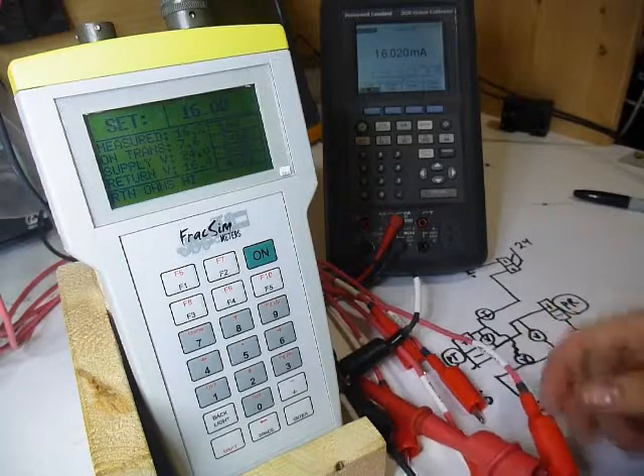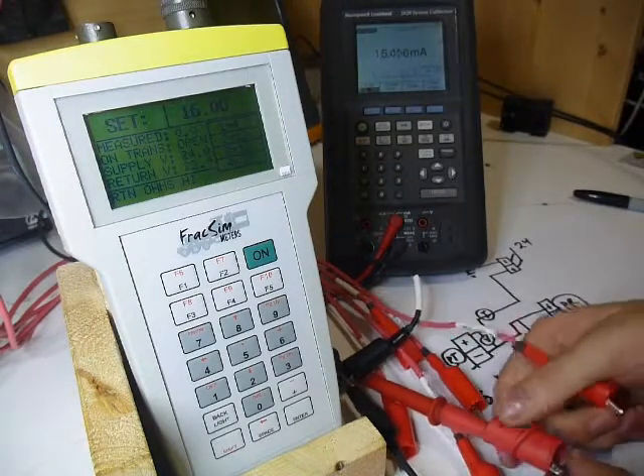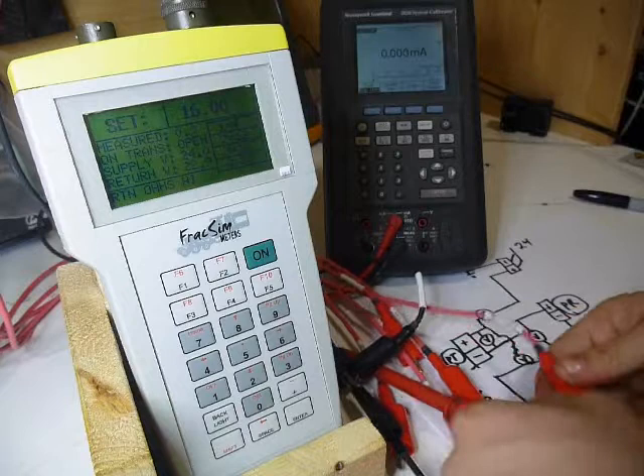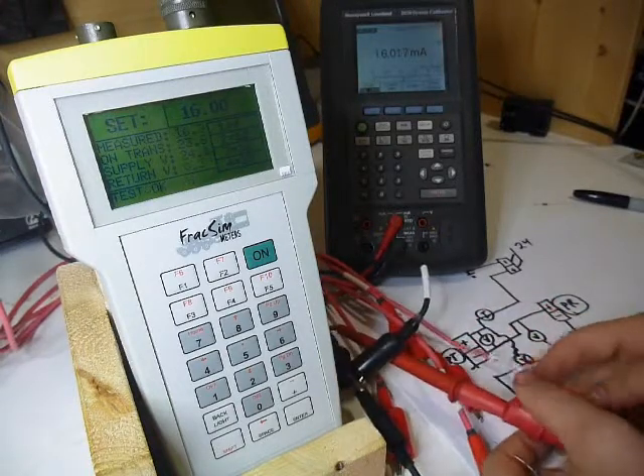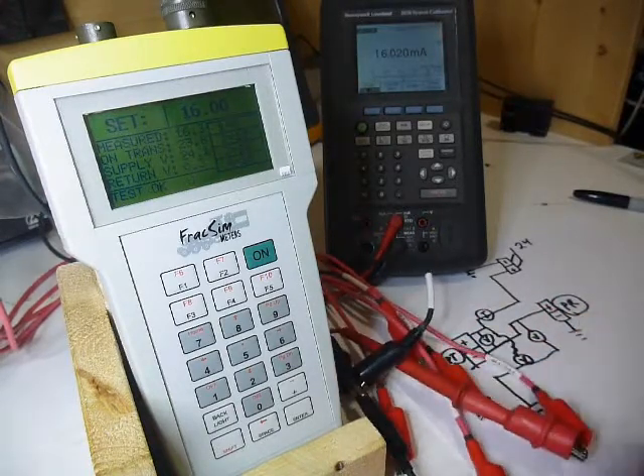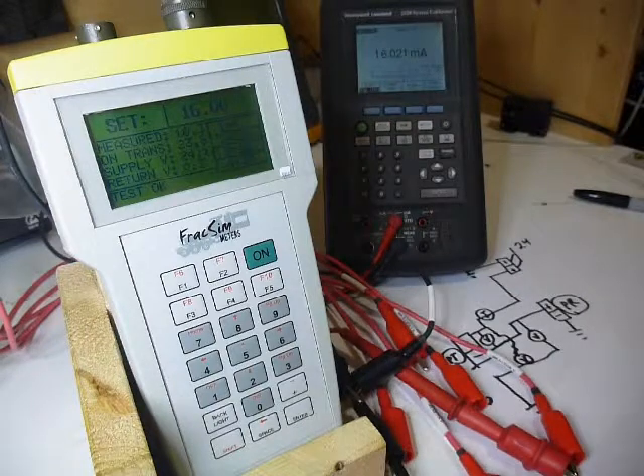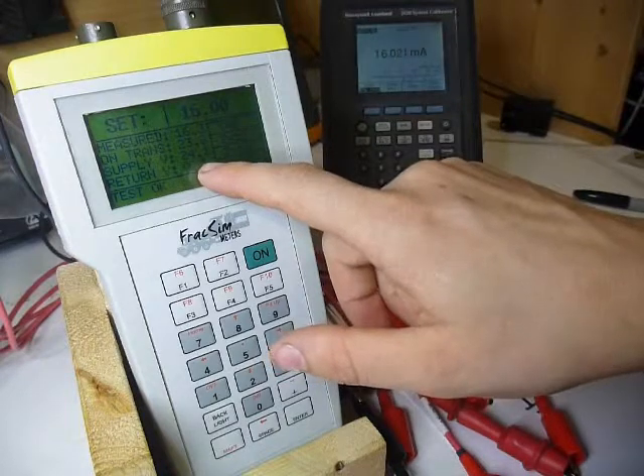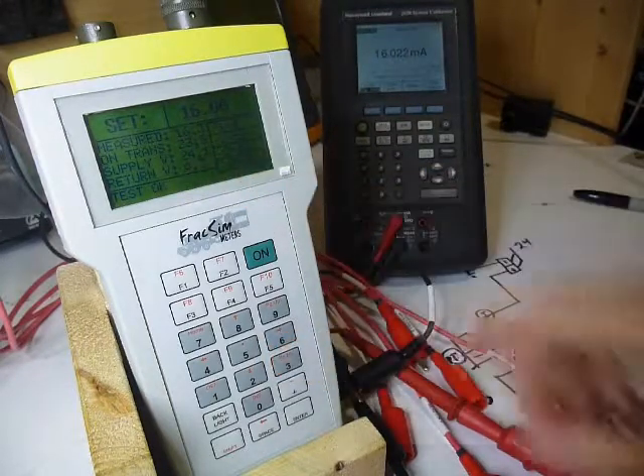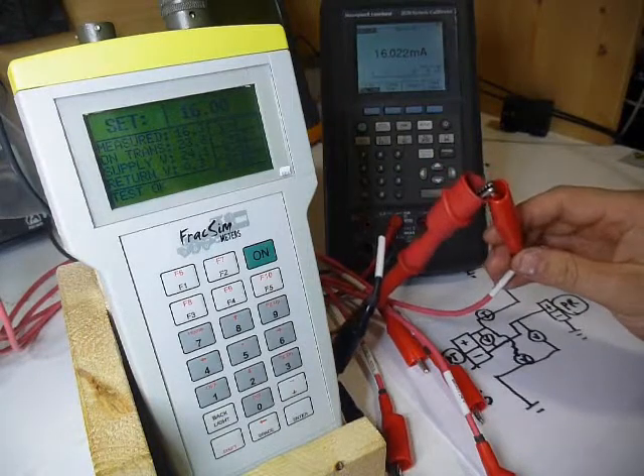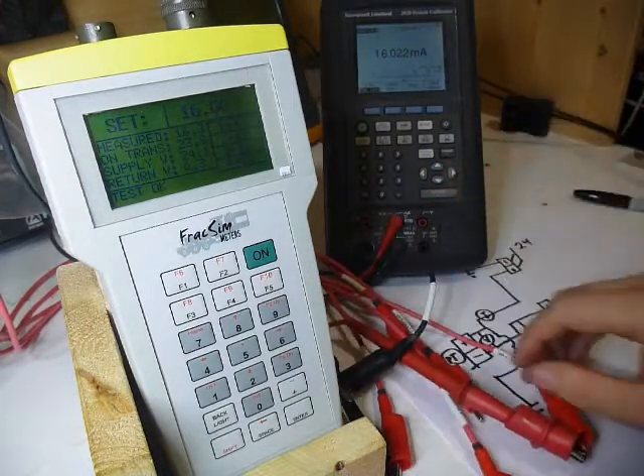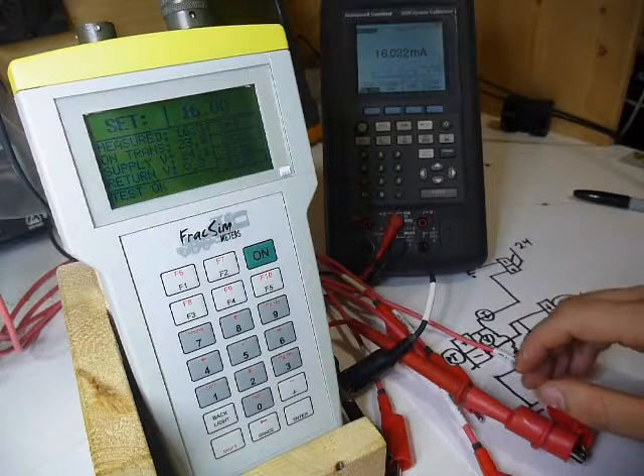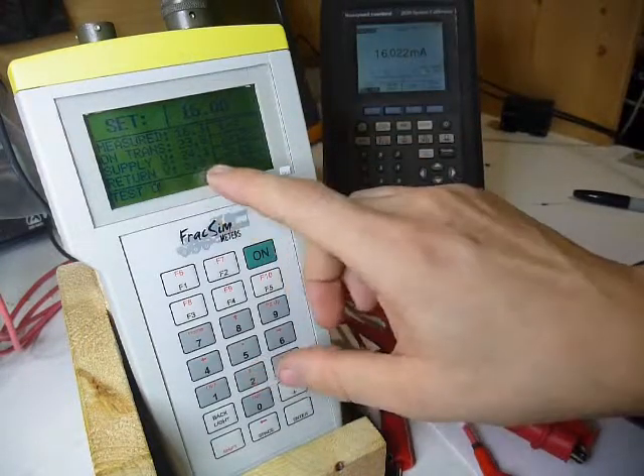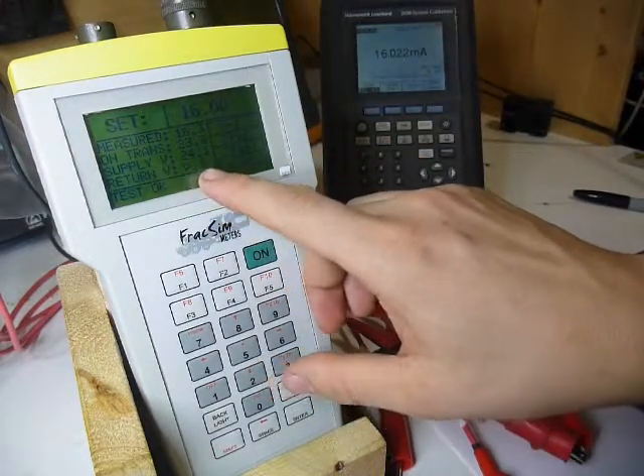Now I'm going to take the 1000 ohm resistor out, and instead of it being on the return side, I'm going to put it on the supply side, and we'll just see what it does. So now we're back. We've got a 24 volt supply. We have a little bit of a voltage drop. It's just shorting it out right now, so theoretically there shouldn't be anything. There might be a little bit just from circuit protection inside of the Fracsim, so that's probably why we're seeing that 0.3 volt small drop there.